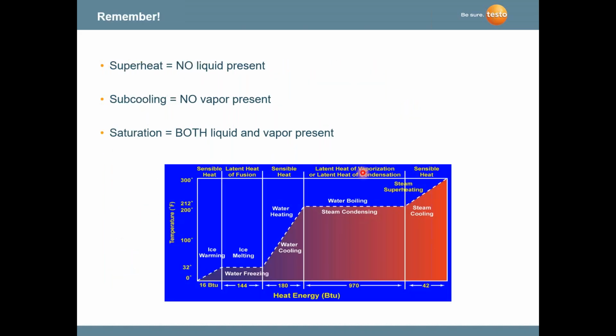If we go back to that graph that we showed earlier, an easier way to remember this is that superheat is everything above the saturation, and there is no liquid present up here in the superheat area. Subcooling is where there's no vapor present, it's all liquid. That would be in this area here. And then saturation is where you have both liquid and vapor present because it's going from one state to another as we increase or decrease pressure.